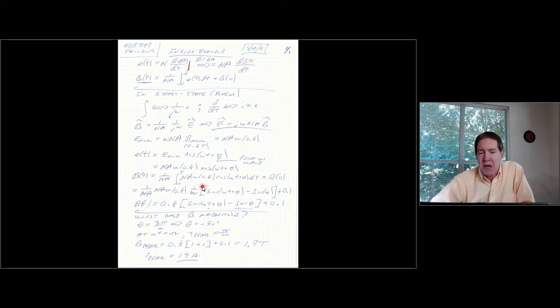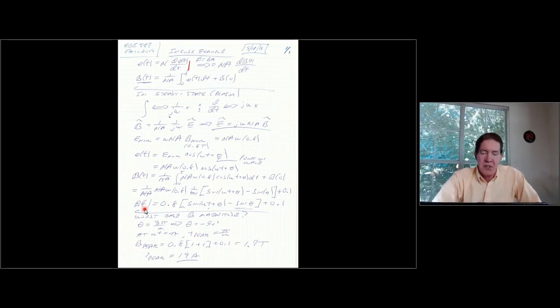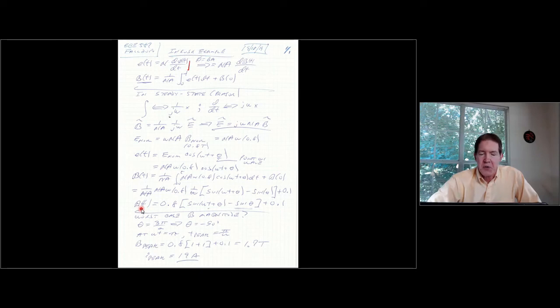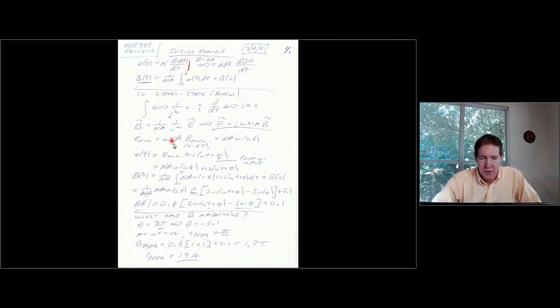To sketch what this looks like during energization, I go back to the formula for B and advance time in steps — maybe one-sixteenth of the first half cycle. For each value of B calculated at each time step, I go back to the BI curve and pick up the corresponding current. I could write a small MATLAB routine to do exactly that.